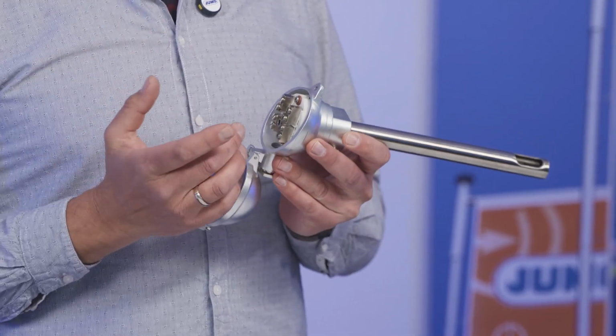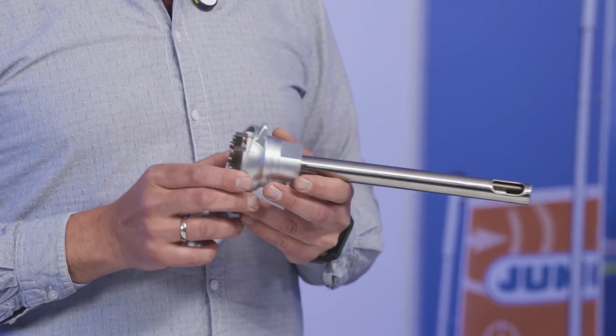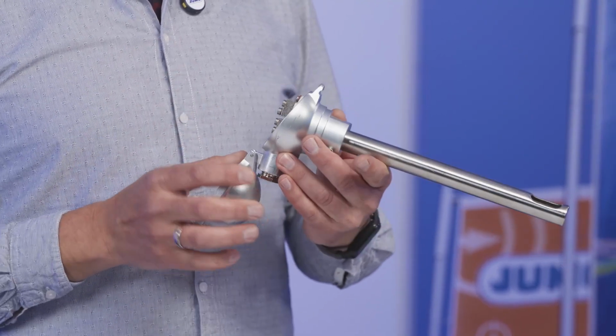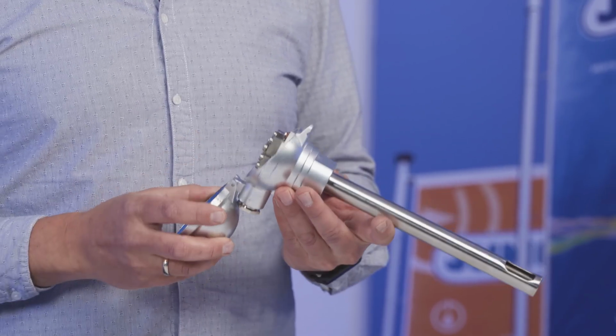Okay. So you mentioned already the system accuracy test, the SAT test. Where do systems fail most often? Do you have any idea, or can you tell us? The systems most often fail because there is no SAT implementation available. That is, there is no entry hole where the reference SAT sensor can be inserted. This is often the case in older systems, and it's recommended to retrofit with a JUMO sensor with a SAT hole inside, because then you always have the same position for the recurring SAT tests. And when the customer uses a new furnace, normally it comes with this kind of sensor. With a SAT hole.